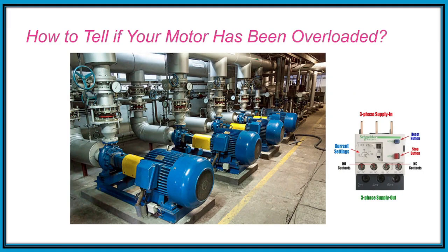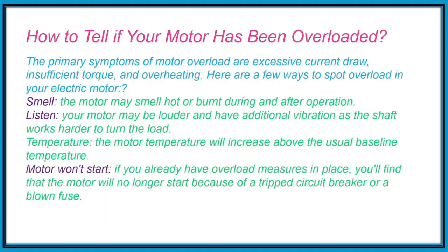How to tell if your motor has been overloaded? The primary symptoms of motor overload are excessive current draw, insufficient torque, and overheating. Here are a few ways to spot overload in your electric motor. Smell. The motor may smell hot or burnt during or after operation.